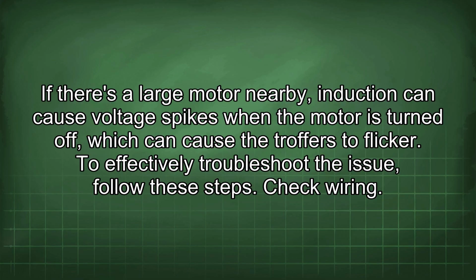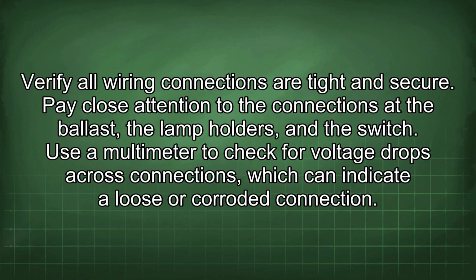To effectively troubleshoot the issue, follow these steps. Check wiring. Verify all wiring connections are tight and secure. Pay close attention to the connections at the ballast, the lamp holders, and the switch. Use a multimeter to check for voltage drops across connections, which can indicate a loose or corroded connection.